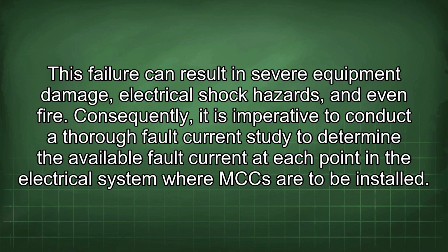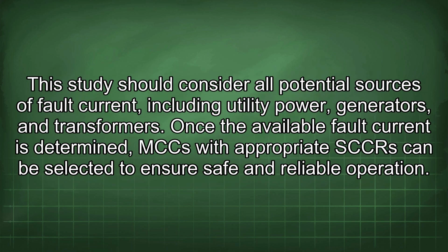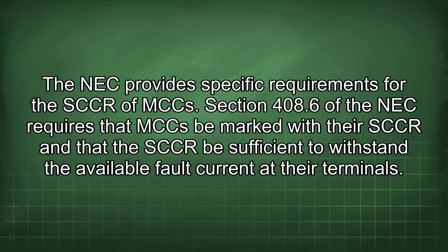Consequently, it is imperative to conduct a thorough fault current study to determine the available fault current at each point in the electrical system where MCC are to be installed. This study should consider all potential sources of fault current, including utility power, generators, and transformers. Once the available fault current is determined, MCC with appropriate SCCRs can be selected to ensure safe and reliable operation. The NEC provides specific requirements for the SCCR of MCC.